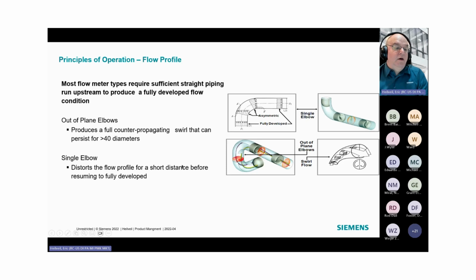Good question. So flow profile, yeah, kind of fits right into what we were discussing just a slide ago. What happens if you don't have just the right flow profile, where you have elbows out of plane or double 90 degrees, or all kinds of flow effects that would disturb the flow, which will change the velocity in different parts of the pipe? So if the velocity is 10 feet per second here, it's 12 feet per second around the inside of a bend, then the problem is, where are you measuring it?